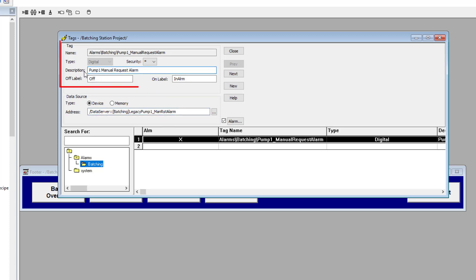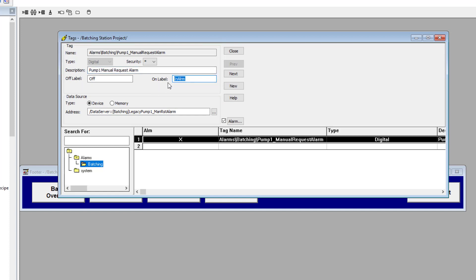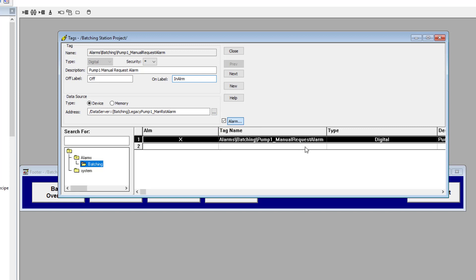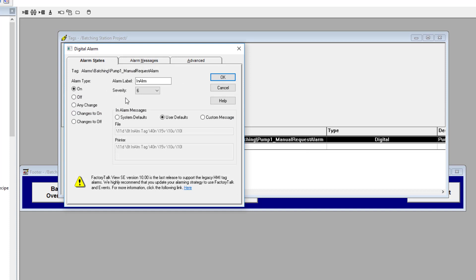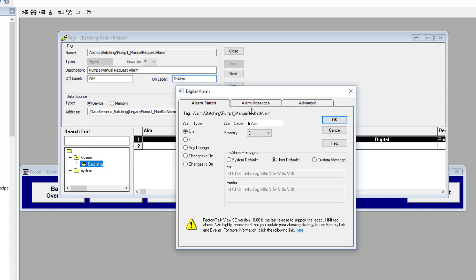What I made is a simple digital alarm tag. This tag is pointing to the correct tag in the PLC. I give it a description, give it a label. What makes this an alarm is checking the checkbox. Checking that box is really where your alarm setup is done, and it's very, very similar to the ALMD.